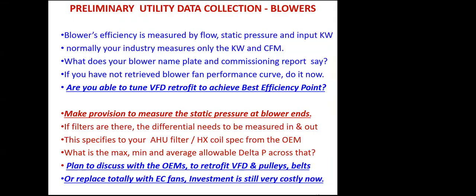Coming to the blowers, efficiency is measured by the flow, the static pressure and the input kilowatt. In 9 out of 10 industries, we don't measure the static pressure at all. So before the energy auditor comes to your premises, give a provision to measure the static pressure at the point of measurement, either the suction or the delivery, whichever you are going to use for the negative side or the positive side. Static pressure measurement is very critical, especially to assess the efficiency of your blower. Your blower can be fine-tuned with a VFD to achieve its best efficiency point. The fan performance of the given blower can be maximized by retrofitting a VFD and resizing the belts and pulleys.